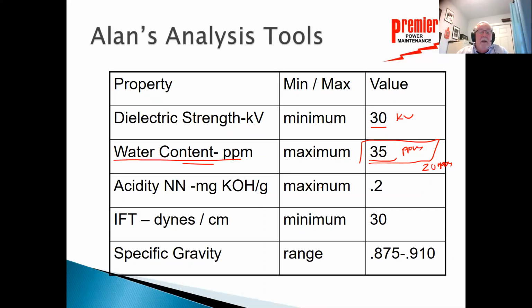Acidity, 0.2 as a maximum. Interfacial tension, minimum of 30 dynes per centimeter. Specific gravity, we want a specific gravity. Those are values that we're looking at and we're going to monitor.